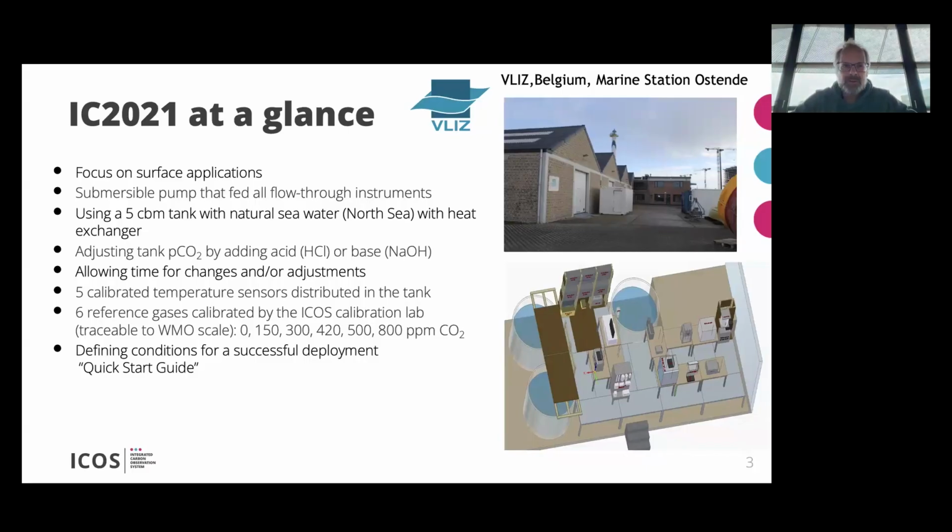because what we wanted to avoid is this blaming and shaming game that we all know. Either the manufacturers blame the scientists that they didn't deploy the instrument right, or the scientists blame the manufacturers that they didn't give the right instructions. One goal was to use this quick start guide during the intercomparison, and maybe improve it so that at the end we have agreed conditions.